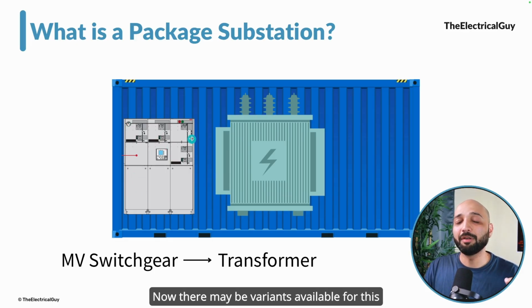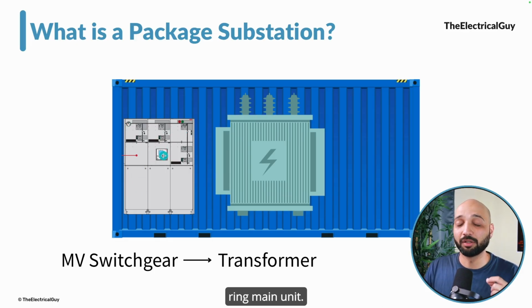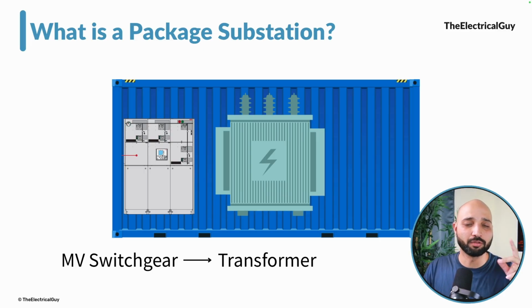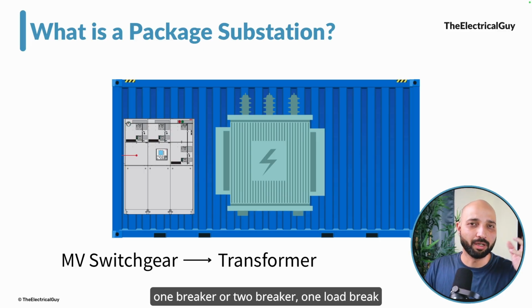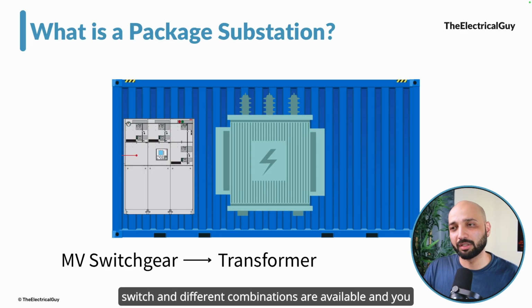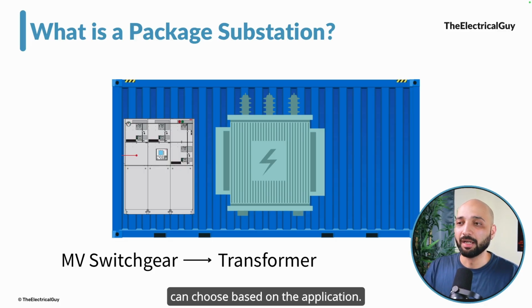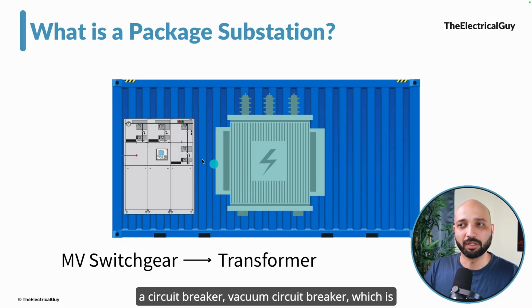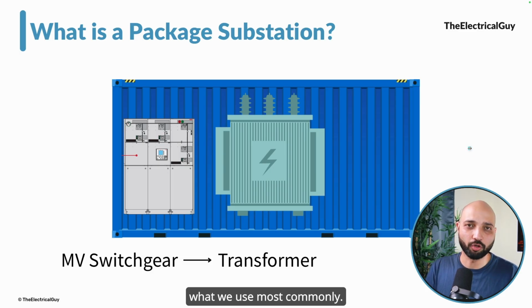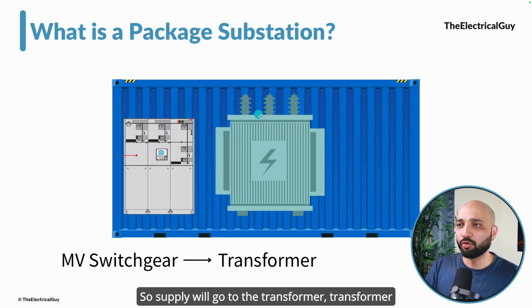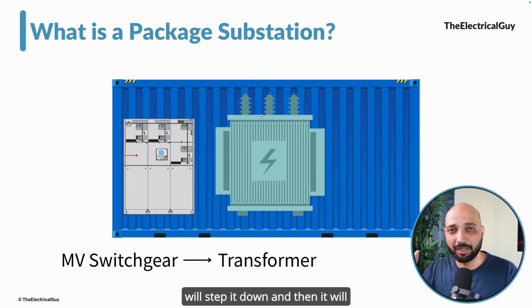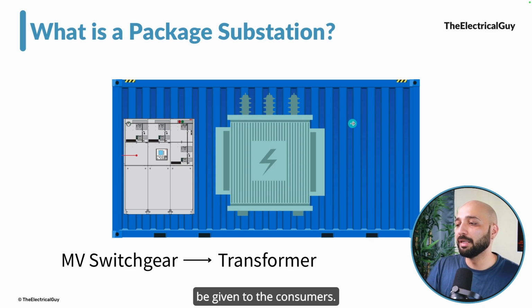There may be variants available for this ring main unit - there can be 2 load break switches, 1 breaker and 1 load break switch, or different combinations, and you can choose based on the application. But since the transformer is one of the most expensive devices, it's mostly protected by a circuit breaker - a vacuum circuit breaker, which is what we use most commonly. So supply goes to the transformer, gets stepped down, and then is given to the consumers.